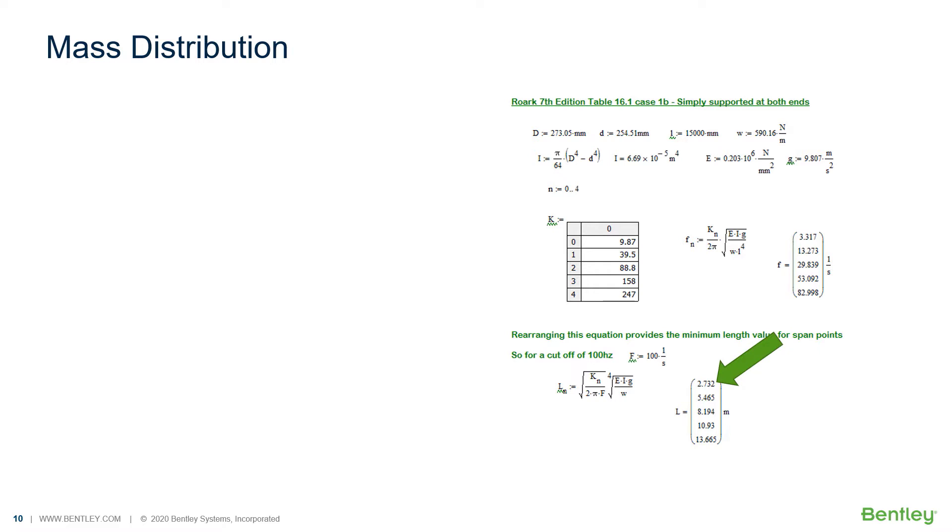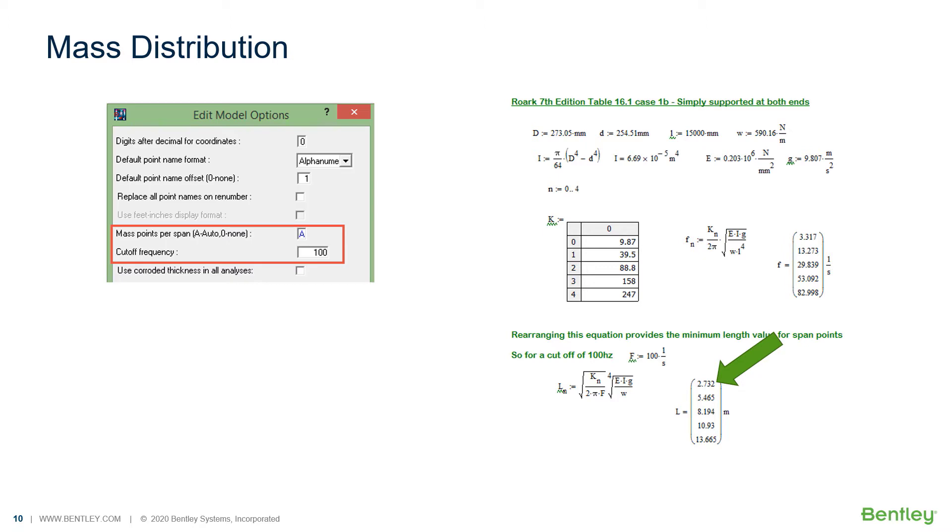If we rearrange the equations, we see the minimum calculated span length is 2.732 meters, or about 9 feet. This is less than the 5 meters or 16 feet that we were seeing in exercise 2. The program has a way to assign mass points at a span length equal to one half of the value calculated by selecting A in the edit model options for mass points per span and entering the desired cutoff frequency, which will be used in this equation.